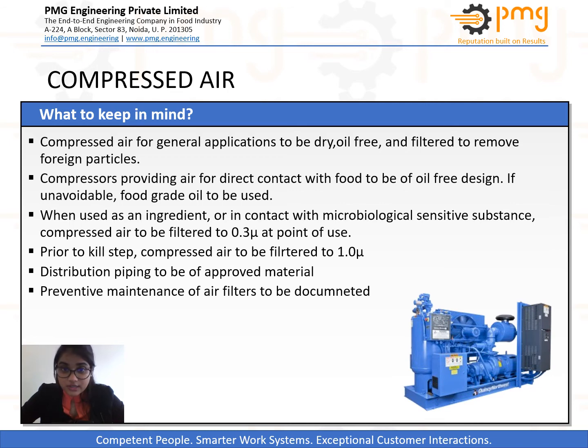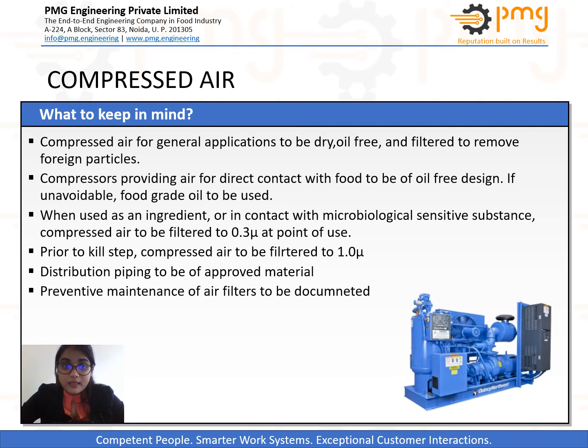Compressed air for general application should be dry, oil-free and must be filtered to remove foreign particles. Compressors providing air for direct contact with food to be oil-free design; if unavoidable, food-grade oil to be used. When used as an ingredient or in contact with microbiologically sensitive substances, compressed air to be filtered using 0.3 micron filters at the point of use. Distribution piping to be of approved material. Preventive maintenance of air filters to be documented.